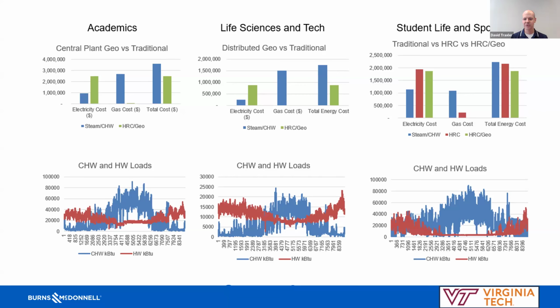Well, in the student life and sports district, there were much lower hot water needs in the summer for dehumidification in these buildings. So the simultaneous load wasn't there. And the winter is fantastic. You can see the chilled water and hot water graphs overlap significantly. And that makes sense because you have sporting events in the winter. You're using the athletic facilities quite a bit. And the dining facilities are being used a lot too. So there's a lot of heat generation, and that could be used for heating the dorms. But you don't have the simultaneous load in the summer. And that was a big reason that you didn't have such significant savings.